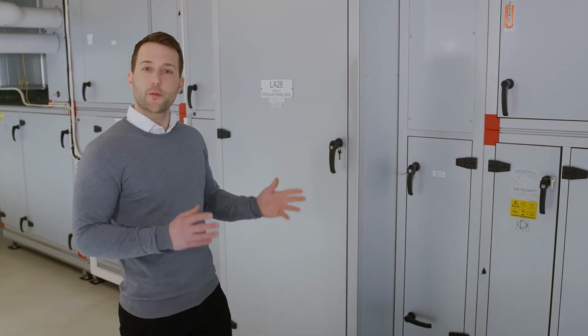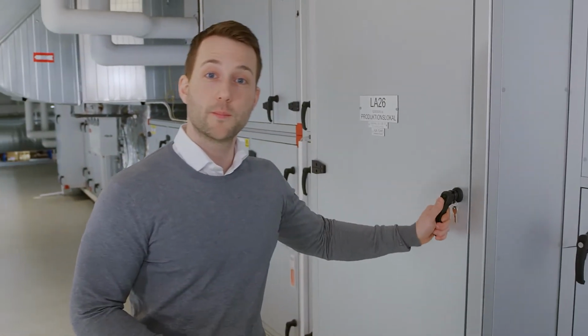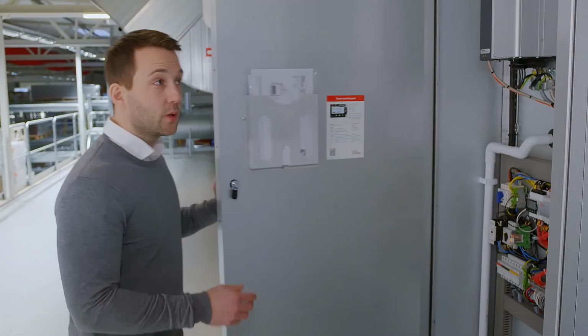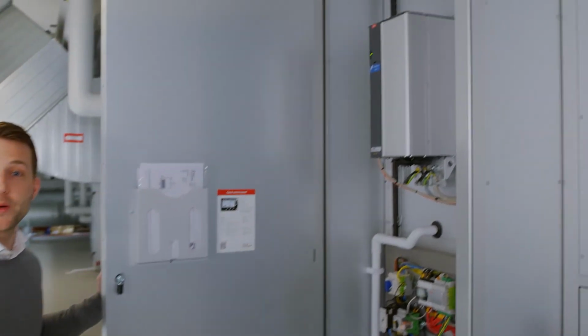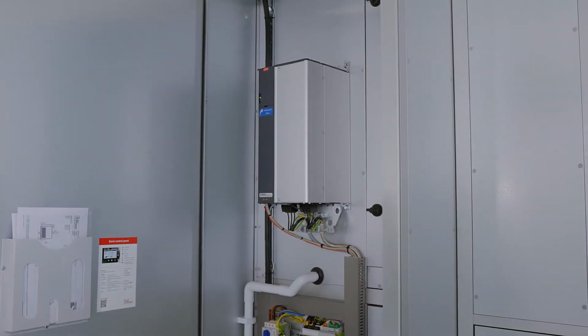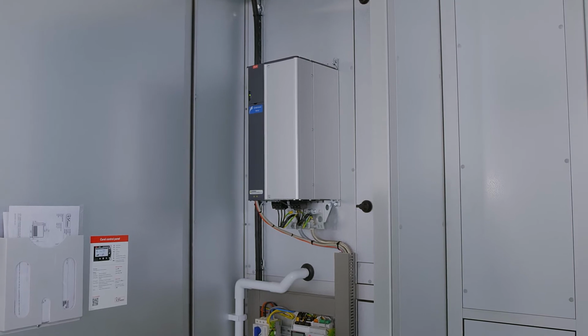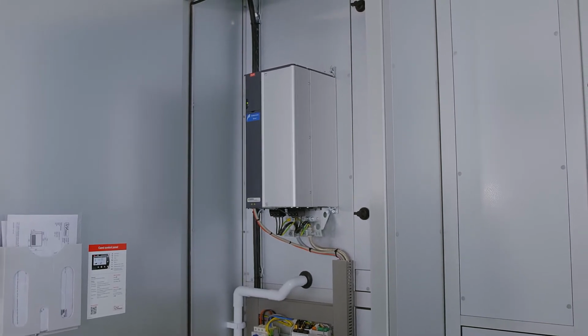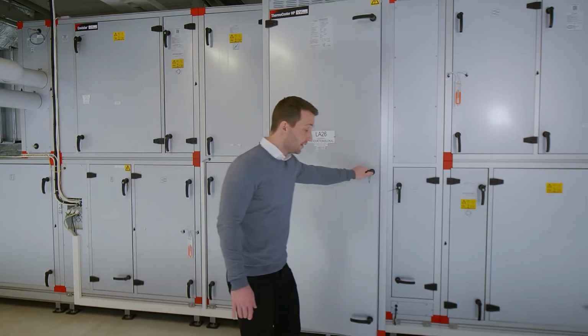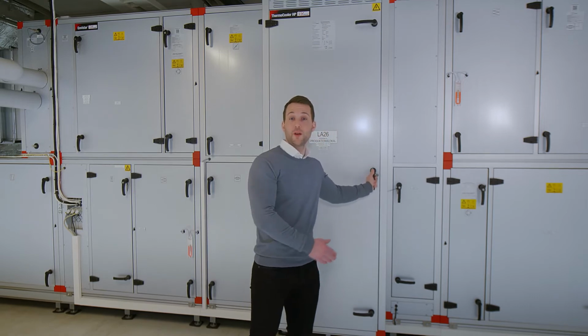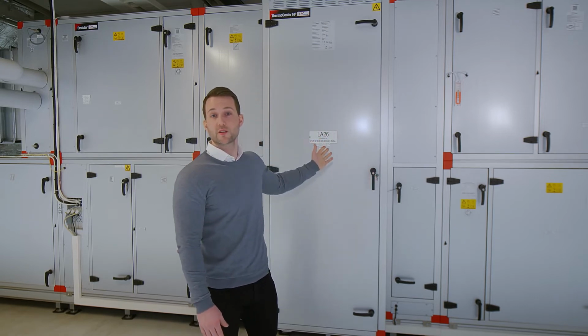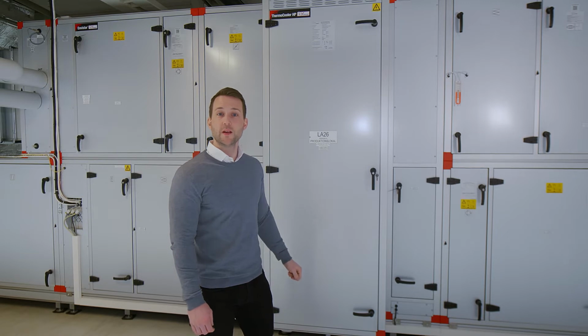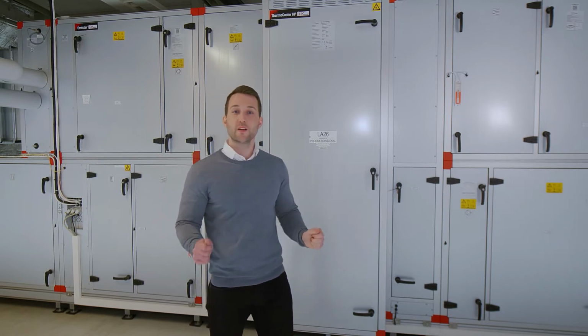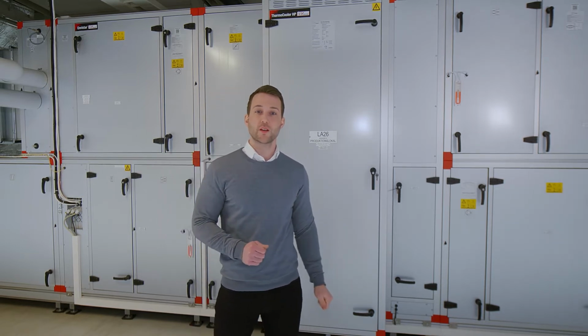Usually we combine our thermal wheels with either our EcoCooler or our Thermocooler. The Thermocooler is controlled by a frequency converter, which allows us to steplessly control the cooling and heating power. The combination between thermal wheel and integrated reversible heat pump Thermocooler HP gives us a dry temperature efficiency of an average 90%.